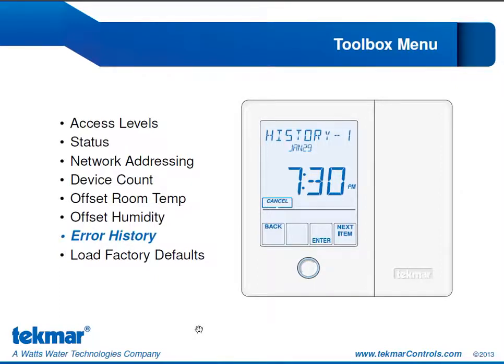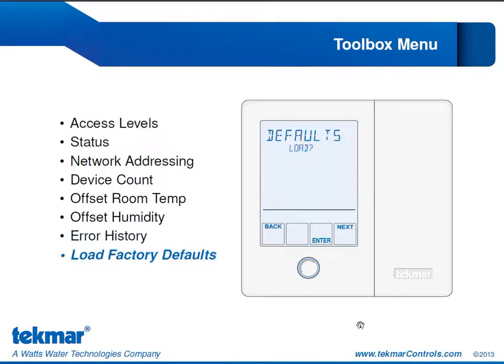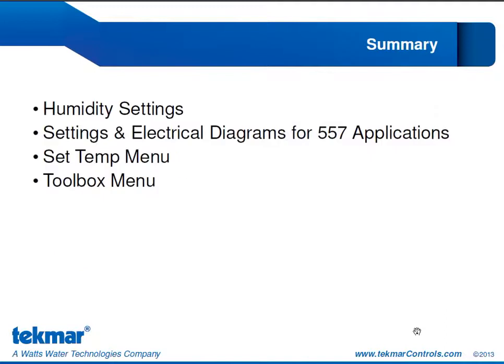A very useful item in the toolbox menu is the error history. So what this does is it displays the last 5 errors that have occurred on the thermostat in the past 30 days. And each error is date and time stamped. So in this example on the screen, we have our first error in the history that occurred on January 29th at 7:30 p.m. And this screen would actually toggle to a screen that shows me the exact error message. If I no longer want that error message to be held in the history, I can press cancel. The toolbox menu is also where I can load the factory default. So if I want to start afresh, I can go in here to load the defaults and maybe configure settings from there.